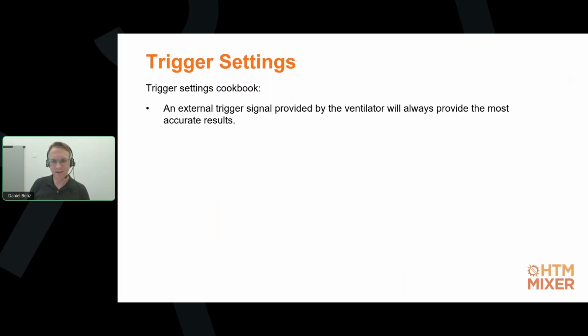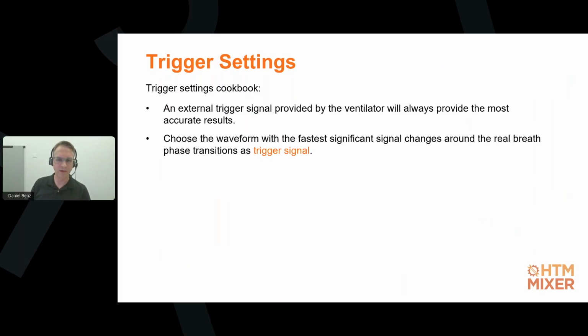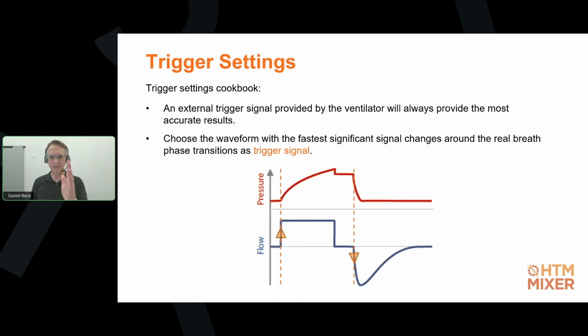So the question is, which waveform do we choose as a trigger signal? The most important thing here is that we choose the waveform with the fastest significant changes around the real breath phase transitions. This means where we have the steepest signal slopes. If we take a look at these examples, we have a pressure waveform up here and a flow waveform down here. The dotted lines indicate the actual real breath phase transitions.